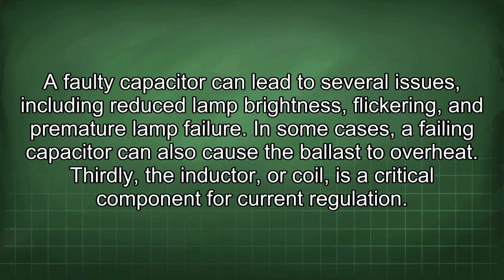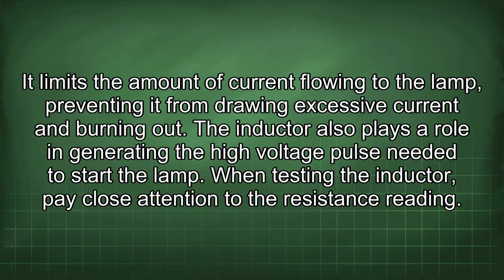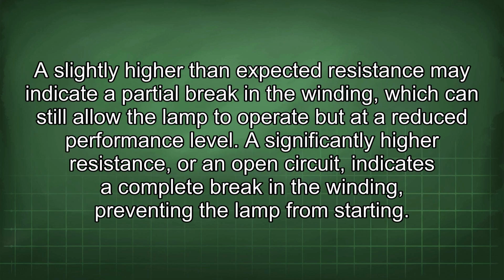Thirdly, the inductor, or coil, is a critical component for current regulation. It limits the amount of current flowing to the lamp, preventing it from drawing excessive current and burning out. The inductor also plays a role in generating the high voltage pulse needed to start the lamp. When testing the inductor, pay close attention to the resistance reading. A slightly higher than expected resistance may indicate a partial break in the winding, which could still allow the lamp to operate but at a reduced performance level. A significantly higher resistance, or an open circuit, indicates a complete break in the winding, preventing the lamp from starting.